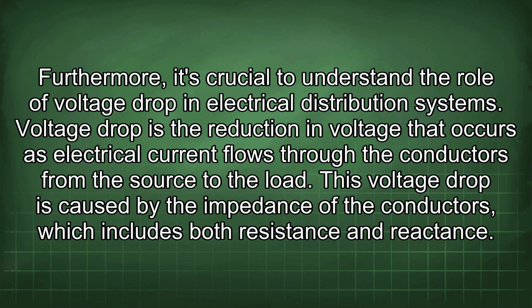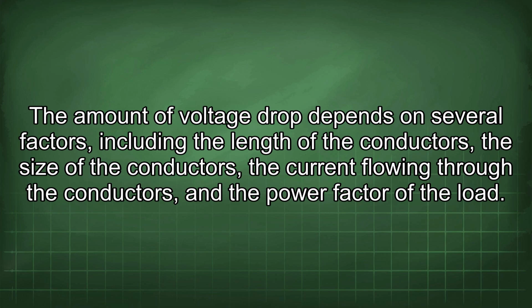Furthermore, it's crucial to understand the role of voltage drop in electrical distribution systems. Voltage drop is the reduction in voltage that occurs as electrical current flows through the conductors from the source to the load. This voltage drop is caused by the impedance of the conductors, which includes both resistance and reactance. The amount of voltage drop depends on several factors, including the length of the conductors, the size of the conductors, the current flowing through the conductors, and the power factor of the load.